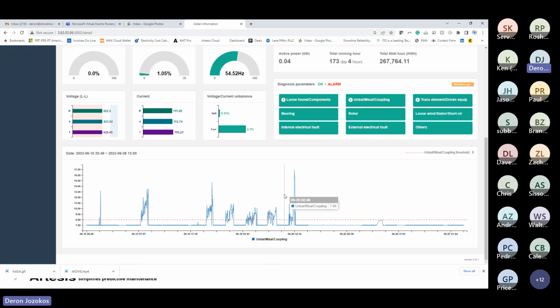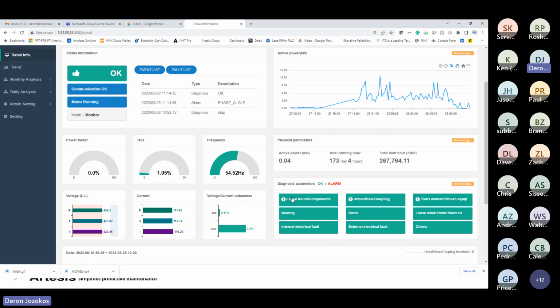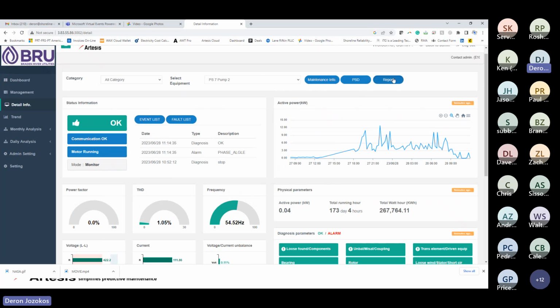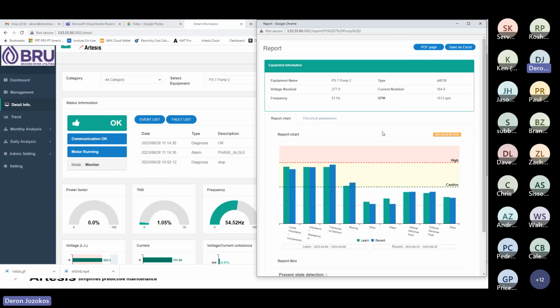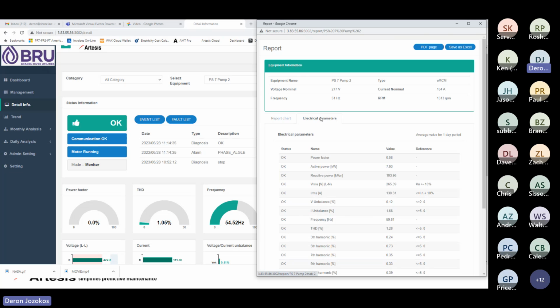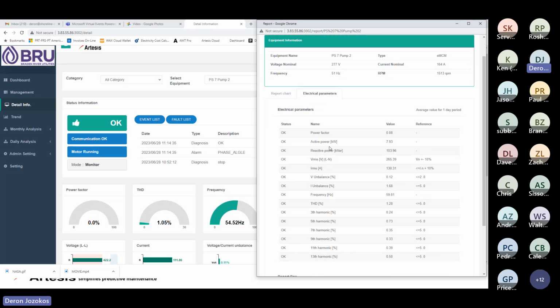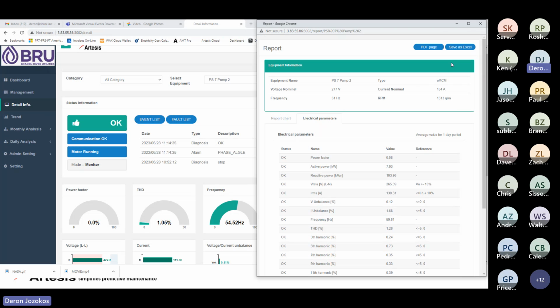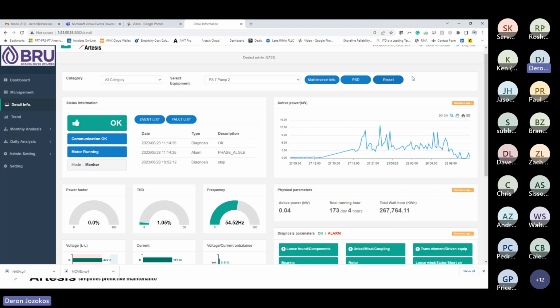That's a quick trend of it, but we have a whole trending page. Up in the top right corner, we'll get our report. Pull the bar graphs here. You can see this thing's been a little bit troubled since we've been monitoring it. So it does need some maintenance, of course. And then all of your electrical parameters on the electrical parameter tab, anything that's in alarm will show up red there. But you don't have to go looking for all these alarms. The system will notify you automatically. It will notify you by email.